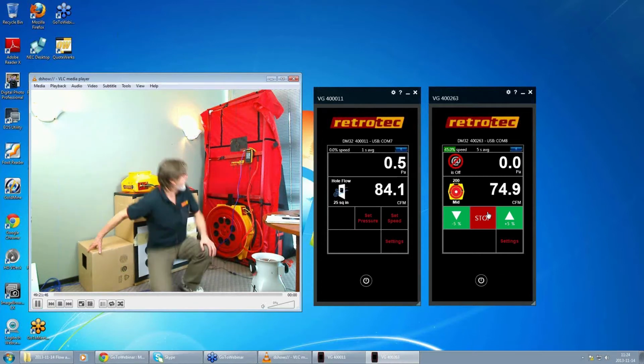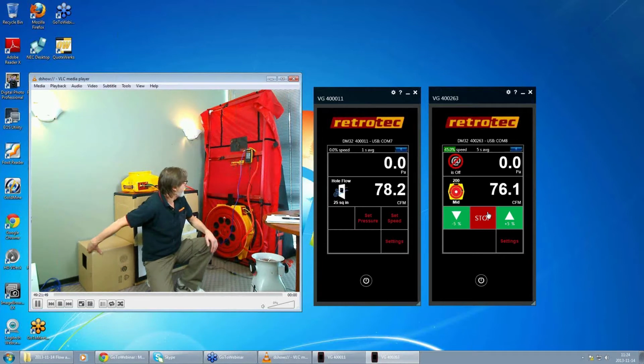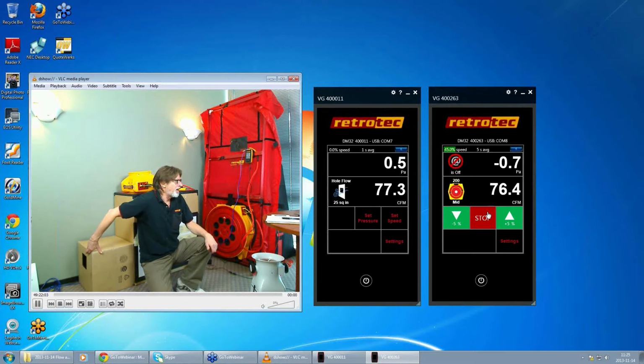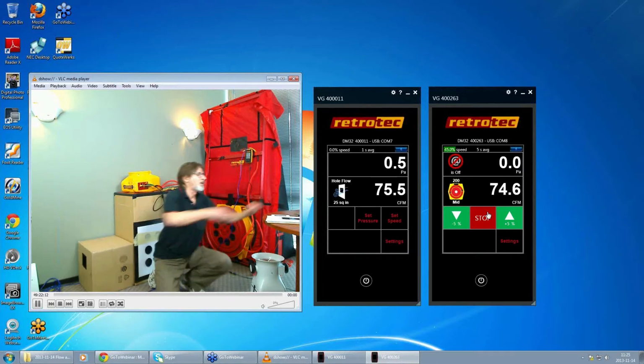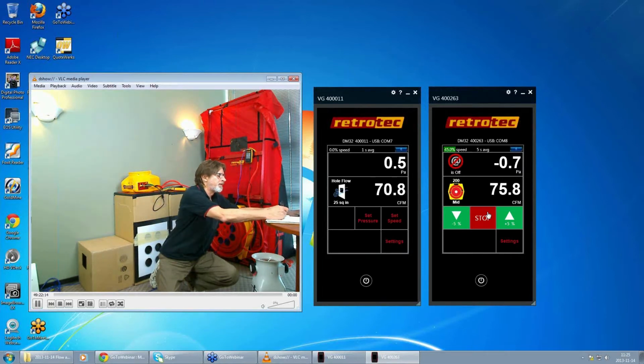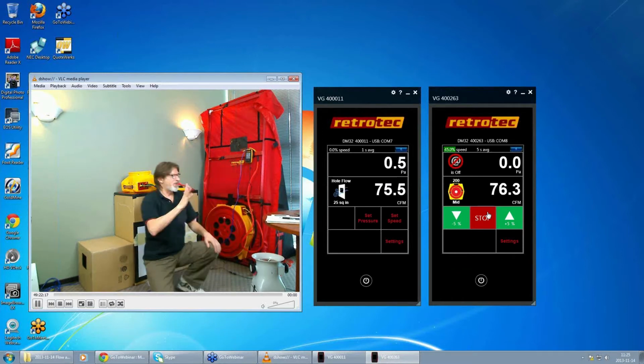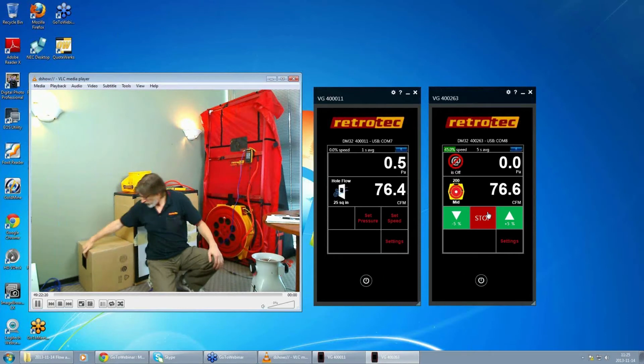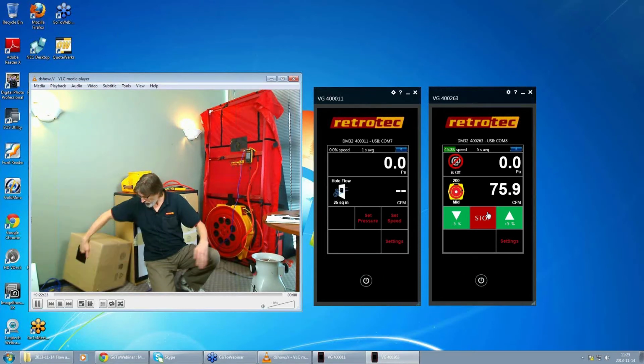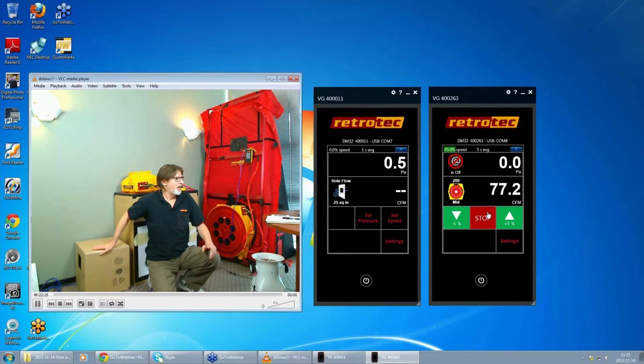And you'll notice that we've got around about the same flow rate on our little flow box as we have on our duct tester. So you can say our duct tester is blowing 76, 77 CFM, and our little flow box is measuring exactly the same thing. Now, as nice as this is in the negative direction, having air flowing into this hole, it probably is not going to work so well on a supply flow.